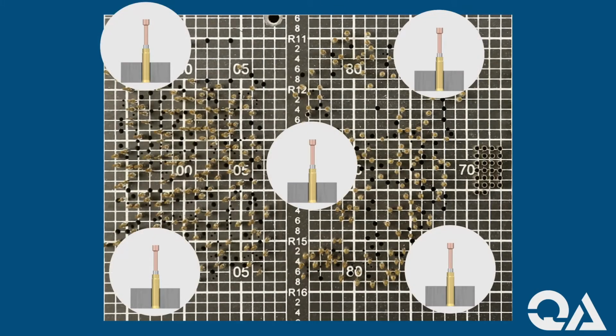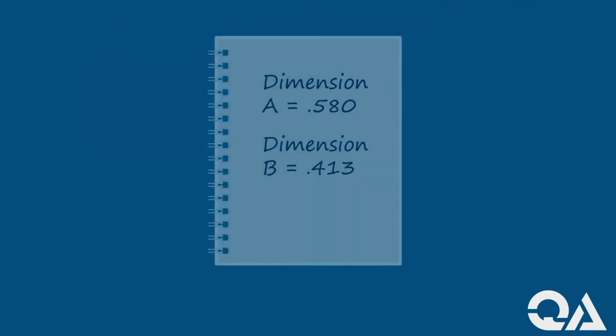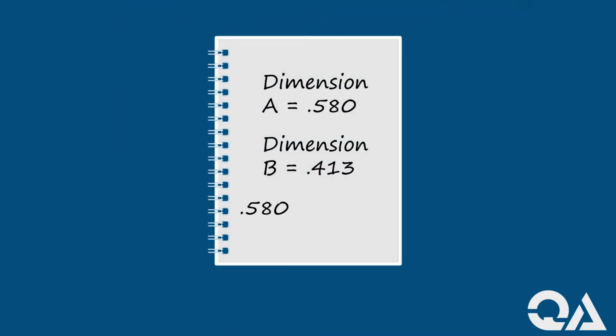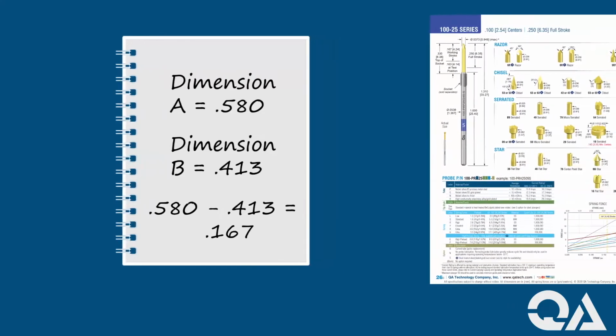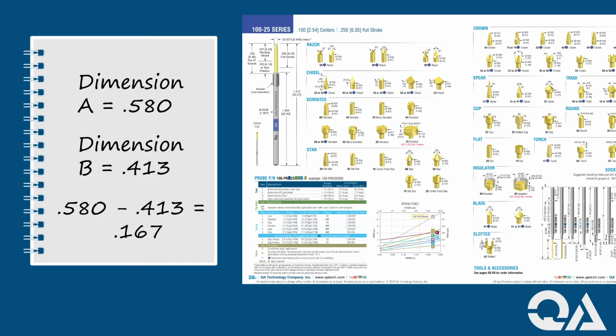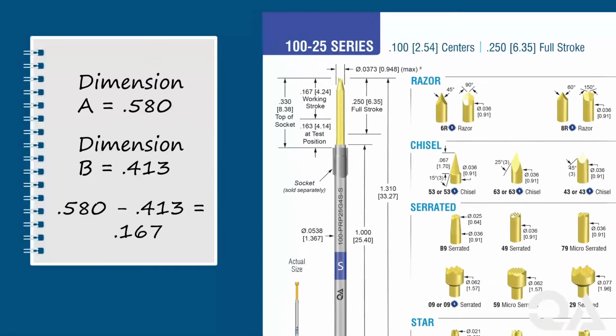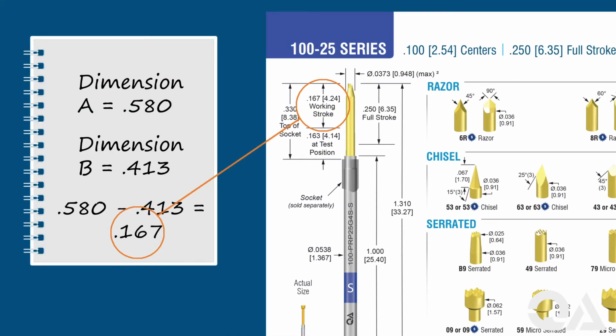Repeat at each indicator probe location to ensure that all probes across the entire field are stroked a similar amount. Compare the difference in height between the original test probe and the indicator probe. This is the amount of plunger stroke that occurs when the fixture is actuated while in production. Compare the actual plunger stroke findings to the working stroke number for that particular probe series. Again, this is typically 2/3 of the full stroke capability.